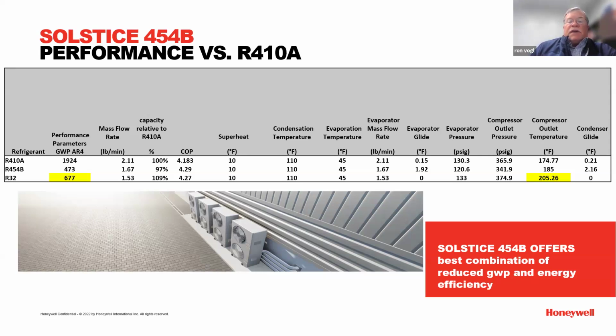This is at 110 condensing, so you can expect some fairly high discharge. A lot of the units accommodate that by either liquid injection or the inverter slowing the compressor down, but I just want you to be aware of that. Other than that, they perform like 410A, which as we mentioned is 50% R32. So that brings you to high pressure and high discharge temp, and you can see the GWPs there.